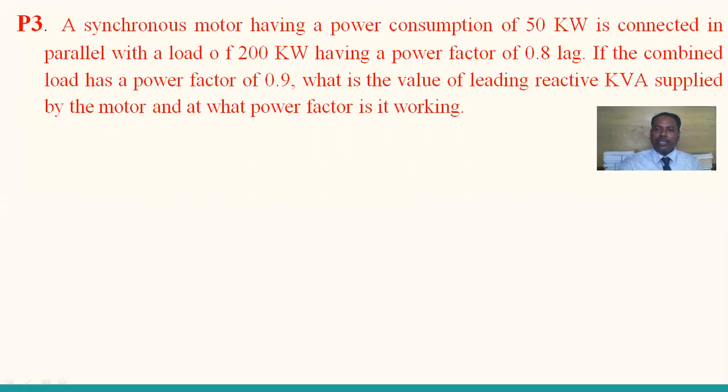So to improve the power factor, a synchronous condenser, or synchronous motor, is connected. This consumes 50 kilowatt additionally so that it injects reactive power into the circuit, so that the power factor is enhanced to 0.9. What is the value of leading reactive kVA supplied by the motor and at what power factor is it working? So this is the problem.